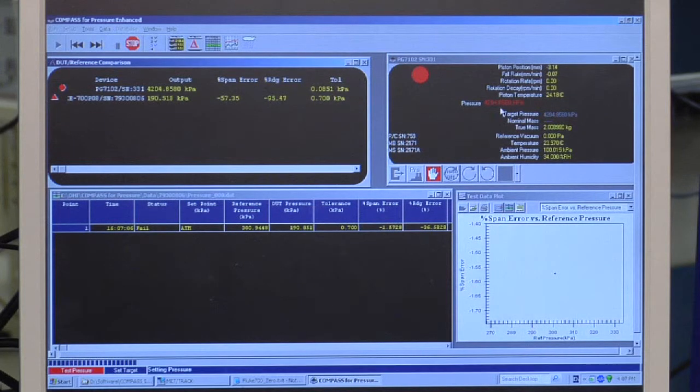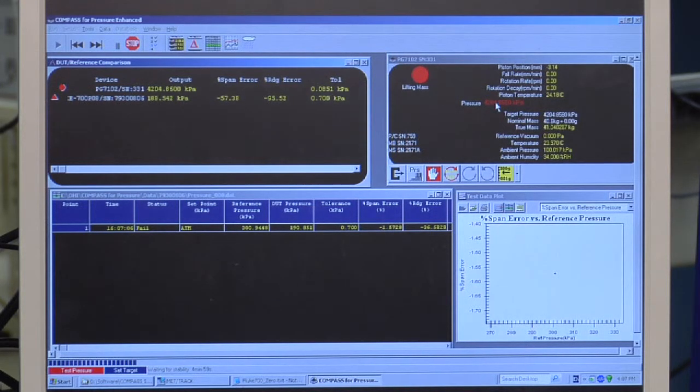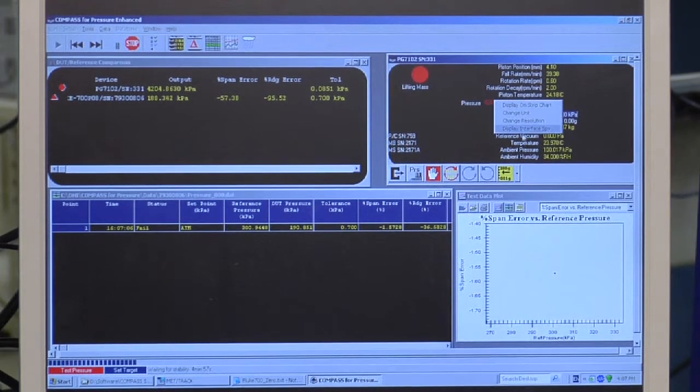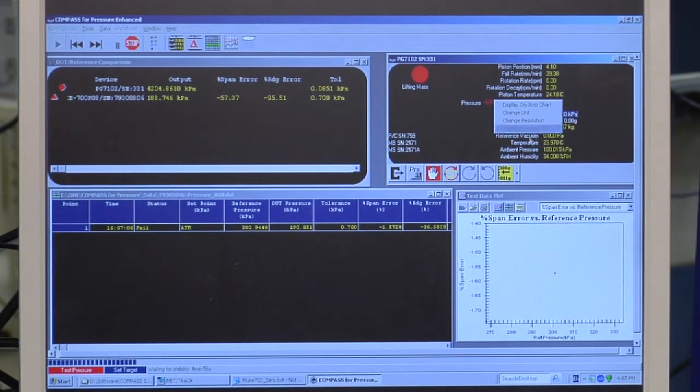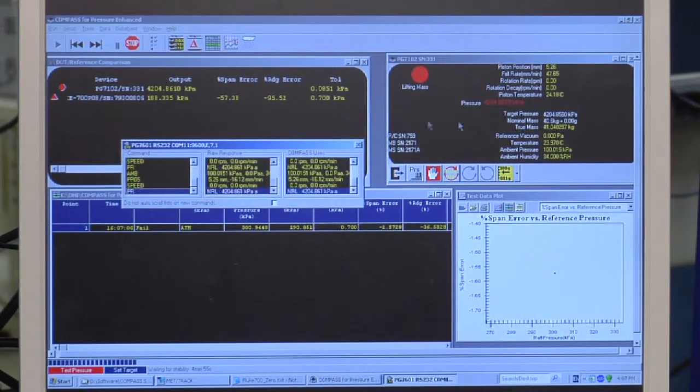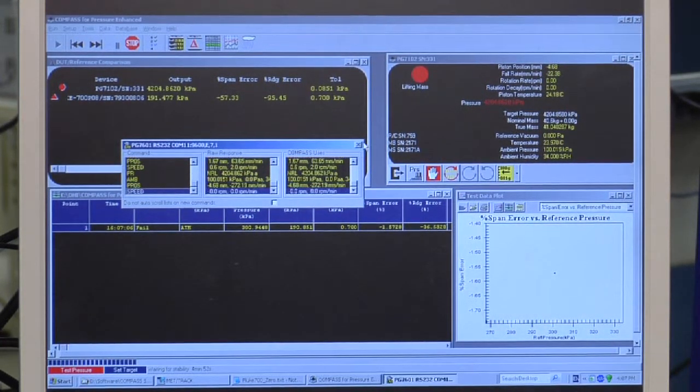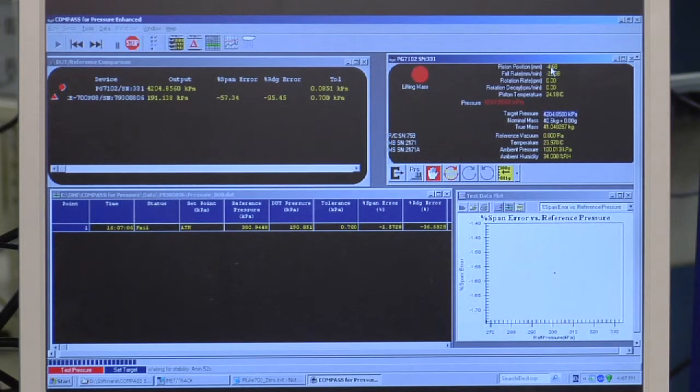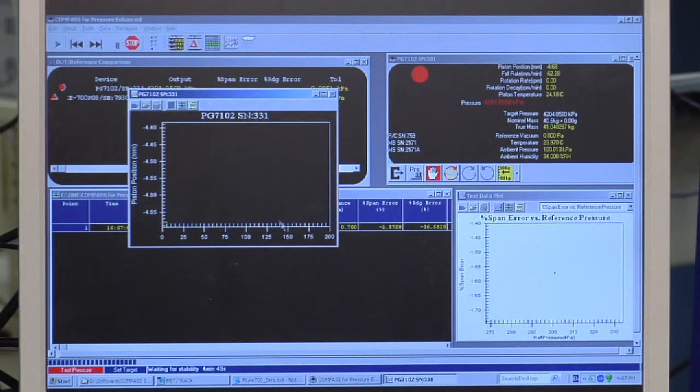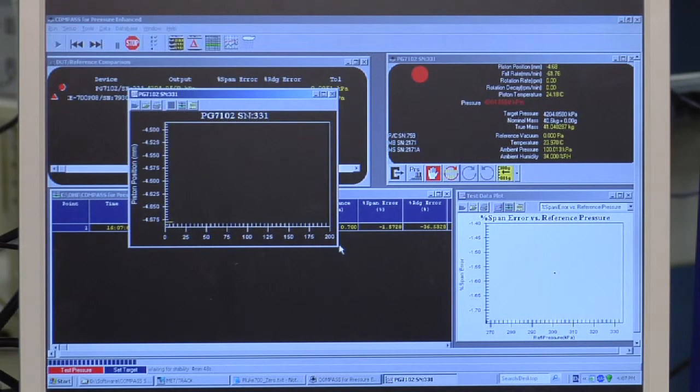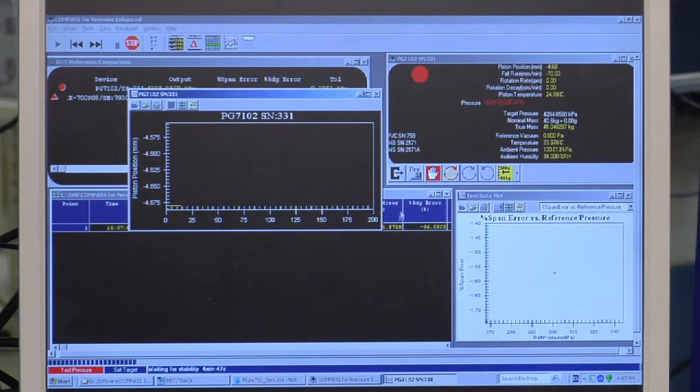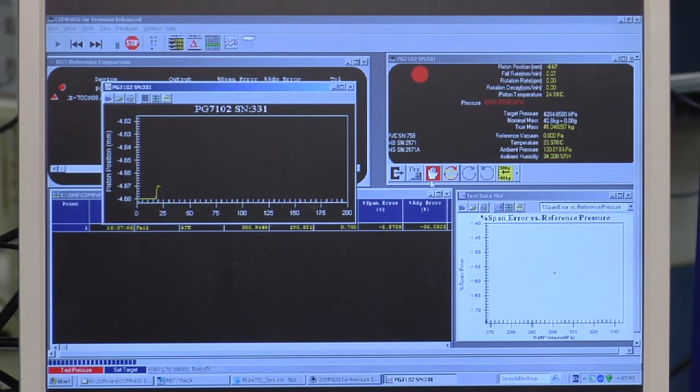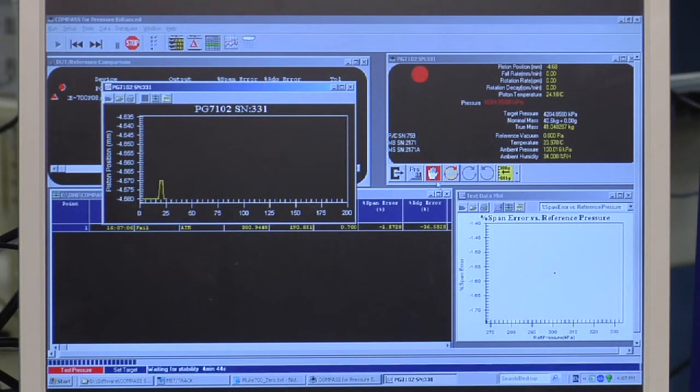The piston gauge run screen or any other run screen, if I click a value, I have a pop-up menu. There's an interface spy so I can see the remote commands. I can click a value and add it to a strip chart. I can also manually control portions of the piston gauge.